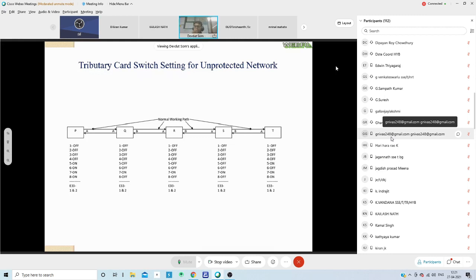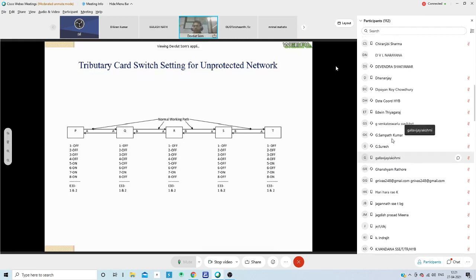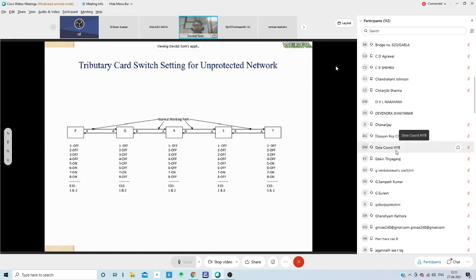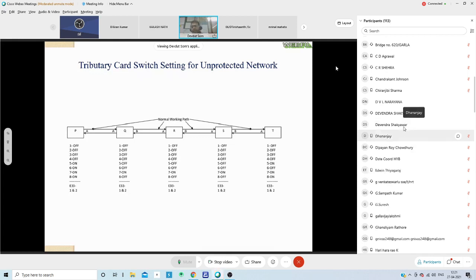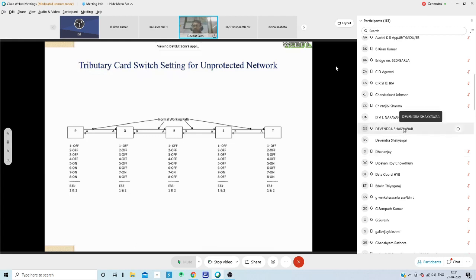Please make sure your earthing is okay and up to the mark. The most you can do, in case of long distance, is provide isolation transformers, which we have already provided. There are also some RDSO spec surge protection devices for voice channels and for both voice and UN channels. You can use them also; that will give you some additional protection.